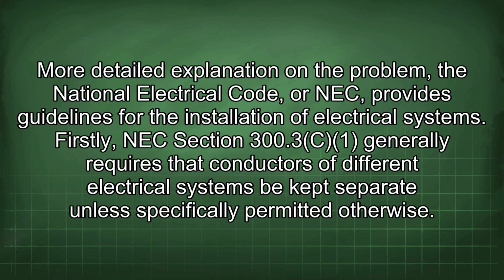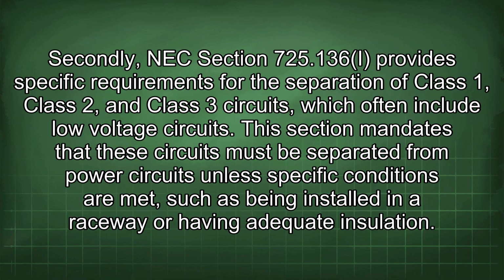More detailed explanation on the problem: the National Electrical Code, or NEC, provides guidelines for the installation of electrical systems. Firstly, NEC Section 300.3 generally requires that conductors of different electrical systems be kept separate unless specifically permitted otherwise. Secondly, NEC Section 725.136(I) provides specific requirements for the separation of Class 1, Class 2, and Class 3 circuits, which often include low-voltage circuits. This section mandates that these circuits must be separated from power circuits unless specific conditions are met, such as being installed in a raceway or having adequate insulation.